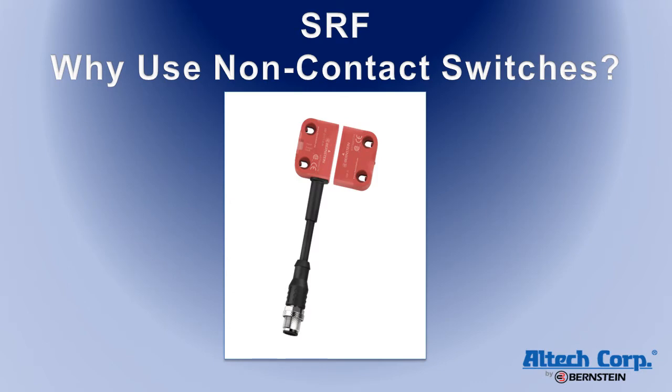Non-contact switches offer solutions to these problems. They have a large misalignment tolerance, up to 13 millimeters. There's no physical contact, so there's no mechanical wear. Uniquely coded actuators are available, so no duplicates are possible. They're easy to wash down with no indentations to catch dirt, and they're easy to install with a minimal amount of alignment issues.